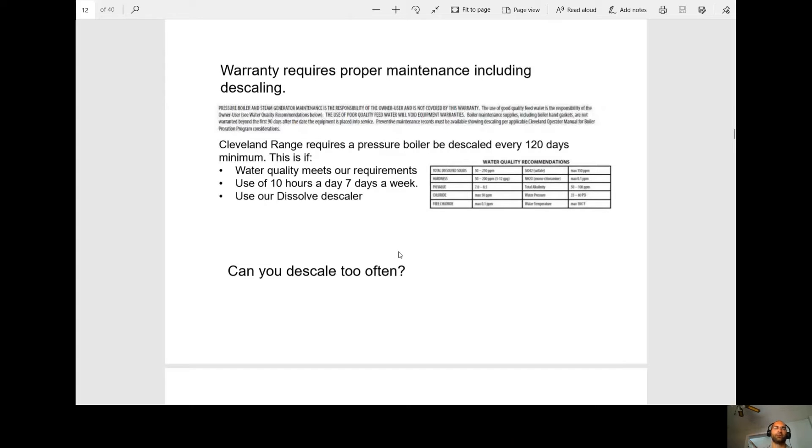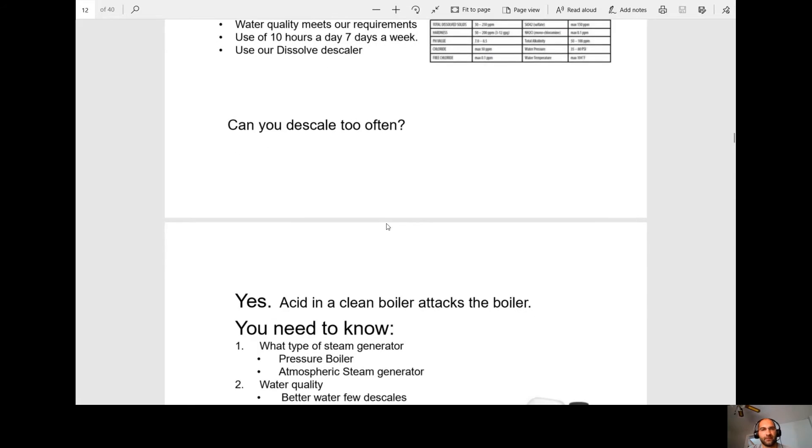So in order to have warranty, you need proper maintenance, which includes descaling. A pressure boiler should be descaled every 120 days, and that's if it meets the water quality. So that's when you do the test, test the water. And that's based on 10 hours a day, 7 days a week. And they want you to use their dissolved descaler. Can you descale too often? Yes. The acids will actually start to eat away at the boiler walls.